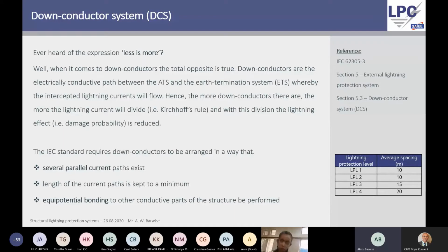And it says to us that when this down conductor passes anything conductive on its way down to Earth, we should ensure bonding. So the equalization of potentials via a direct bond has to be practiced all the way down from the top to the bottom.